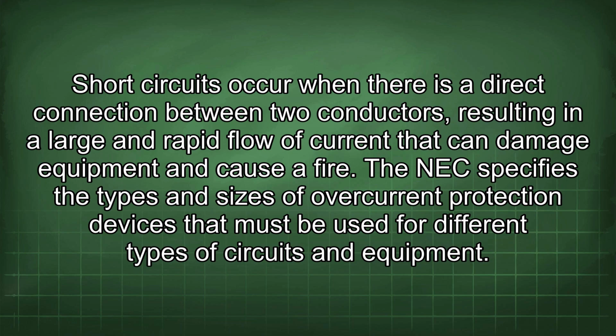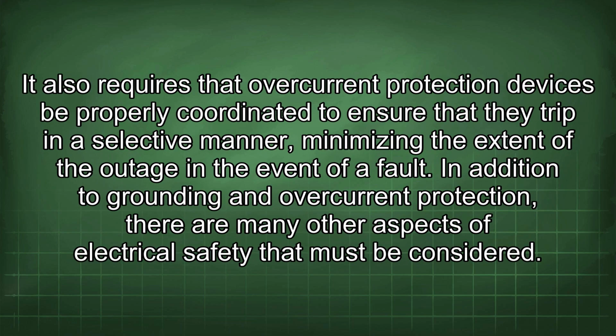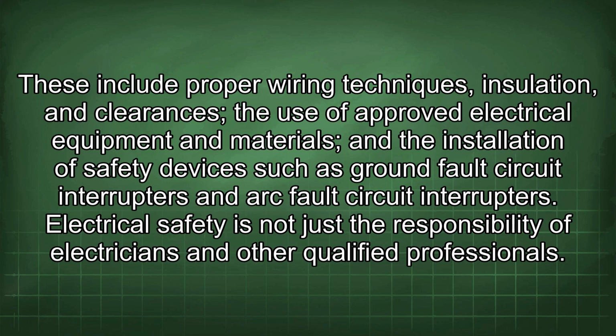The NEC specifies the types and sizes of overcurrent protection devices that must be used for different types of circuits and equipment. It also requires that overcurrent protection devices be properly coordinated to ensure that they trip in a selective manner, minimizing the extent of the outage in the event of a fault. In addition to grounding and overcurrent protection, there are many other aspects of electrical safety that must be considered. These include proper wiring techniques, insulation and clearances, the use of approved electrical equipment and materials, and the installation of safety devices such as ground fault circuit interrupters and arc fault circuit interrupters.